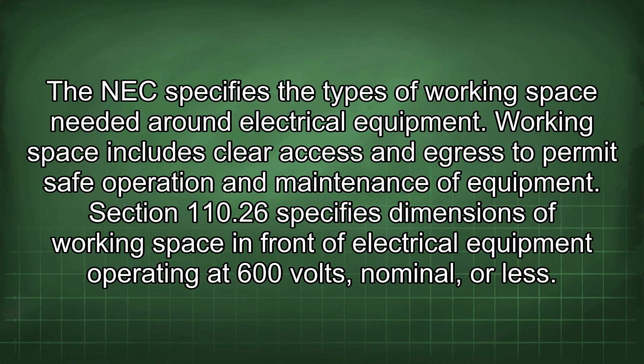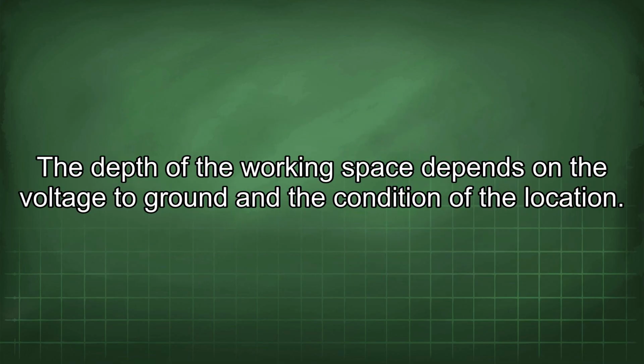The NEC specifies the types of working space needed around electrical equipment. Working space includes clear access and egress to permit safe operation and maintenance of equipment. Section 110.26 specifies dimensions of working space in front of electrical equipment operating at 600 volts, nominal or less. The depth of the working space depends on the voltage to ground and the condition of the location.